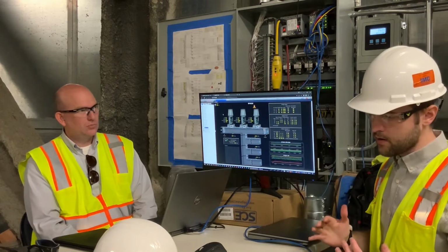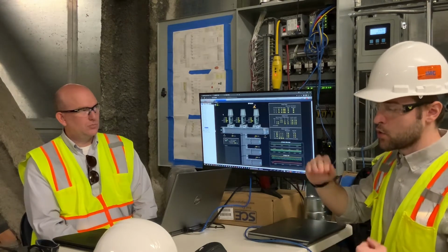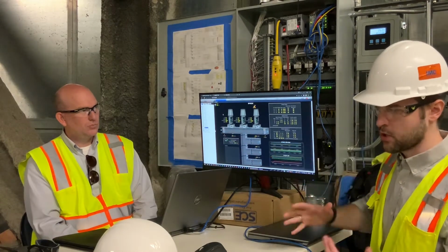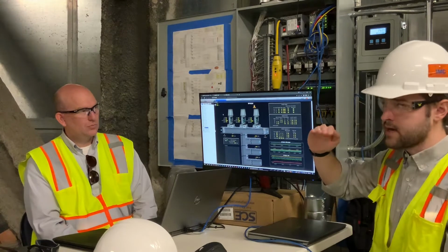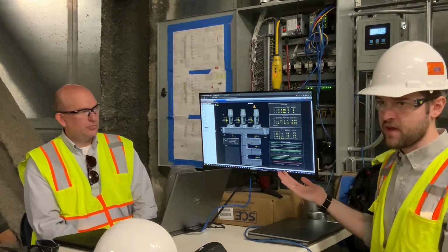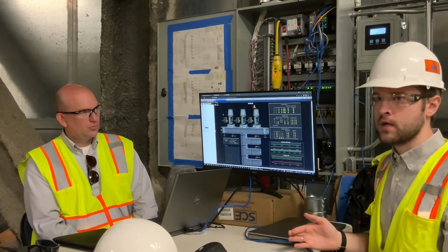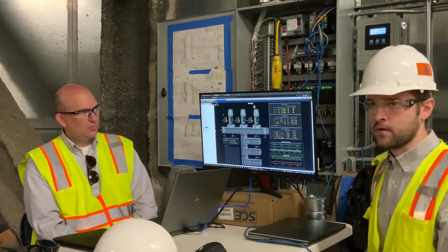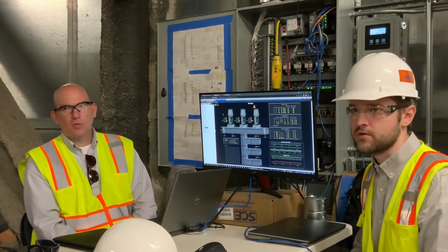Under that scenario, if your dampers are closed, normally if you just had one fan when we first started the system, that fan will ramp up to 95, 100%. It'll bring on another fan. It's designed to always run one or two fans depending on the pressure requirements of your duct.